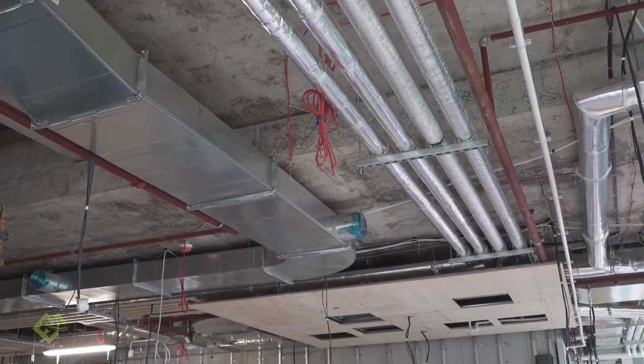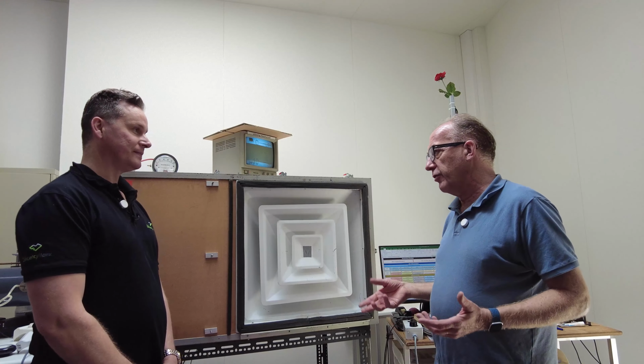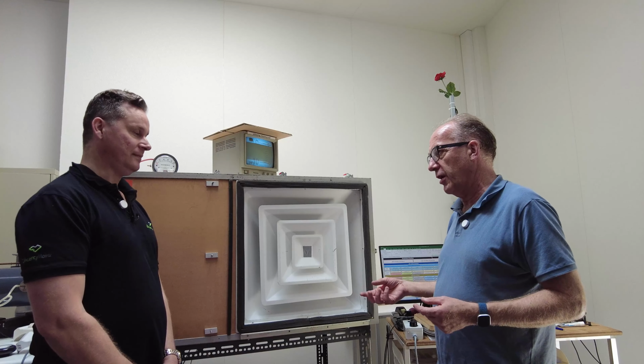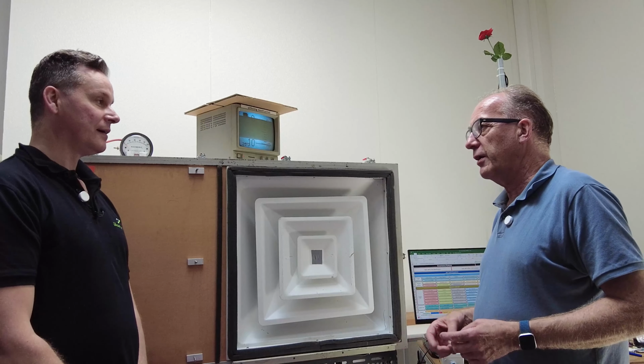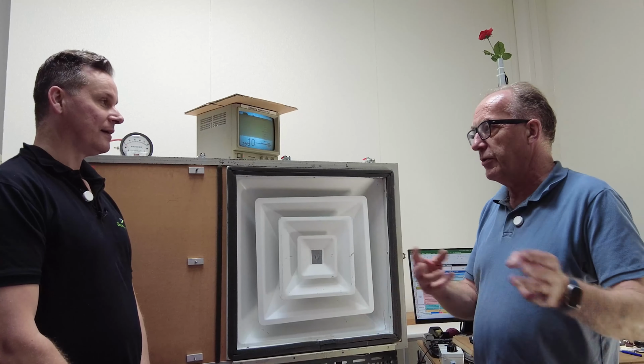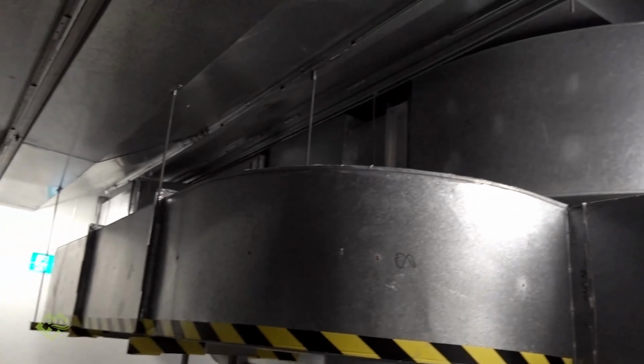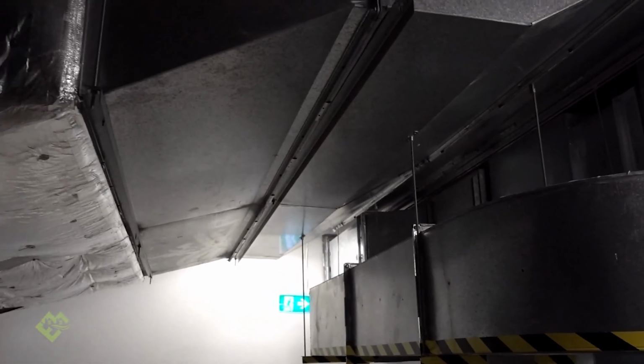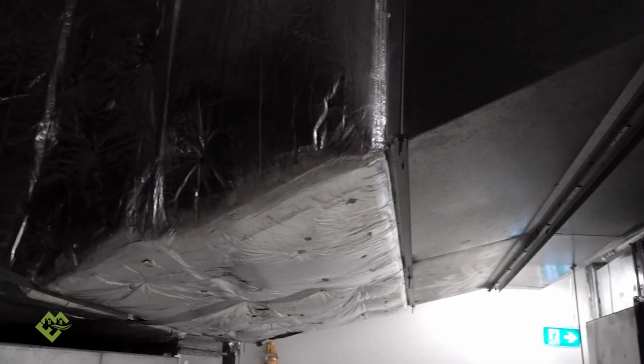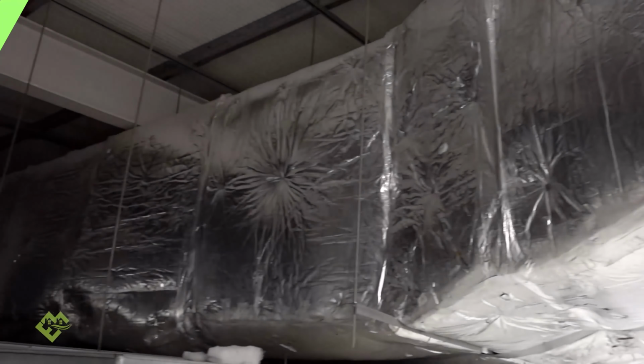Yeah, of course. Again, as an example, the US. In the US, the residential flows are already quite high. And there are commissioners there that actually use the total flow measurement and the Flowfinder to estimate duct leakage. And if they have a lot of duct leakage, they start looking for it. That's interesting. Because duct leakage is one of those things that we all hope don't exist. Yeah. But in reality, it's actually quite prevalent.